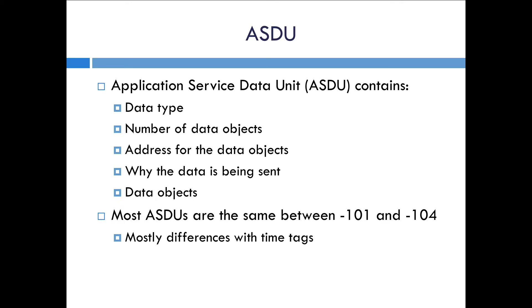ASDU is an application service data unit, and it's a concept used at the application layer. The ASDU always includes the type of data which is contained, the number of data objects in that unit, the addressing for those data objects, the cause of transmission — basically why the data is being sent — and the data objects themselves.